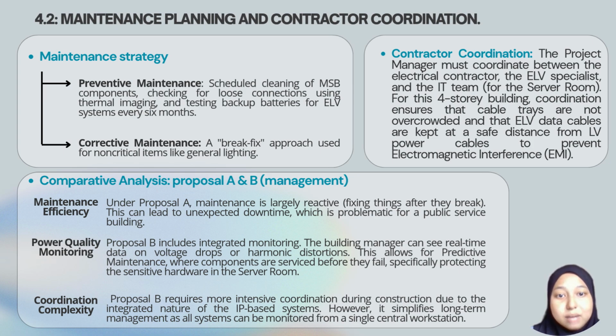This can lead to unexpected downtime, which is problematic for a public service building. Next is the power quality monitoring. Proposal B includes integrated monitoring. The building manager can see real-time data on voltage drop or harmonic distortion.